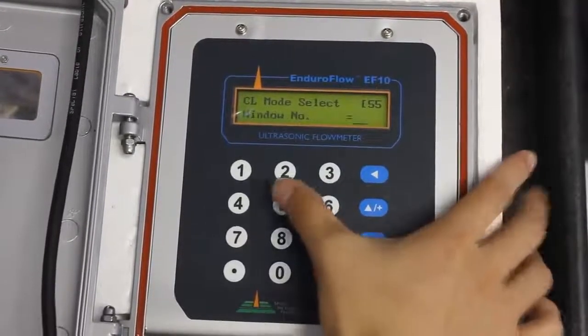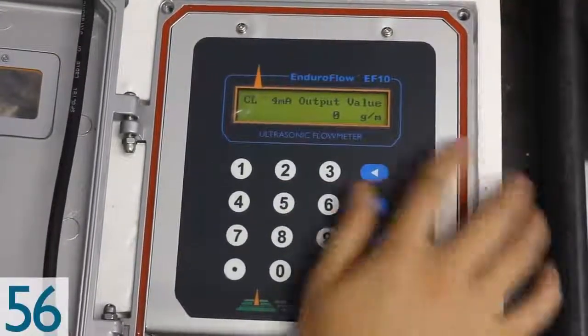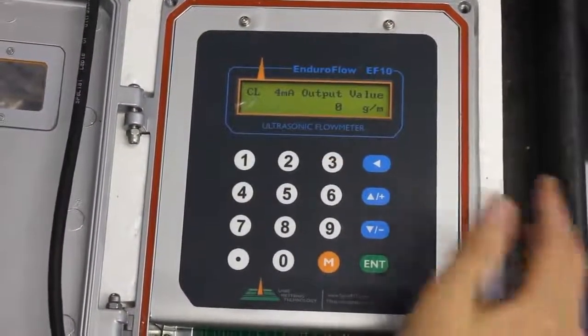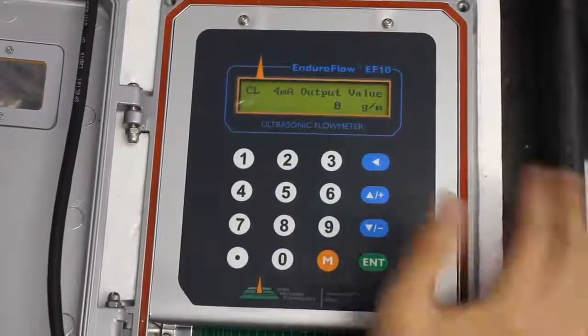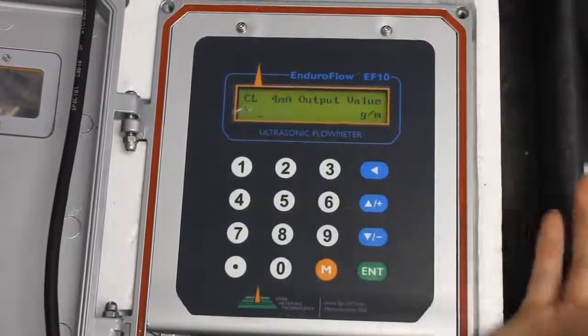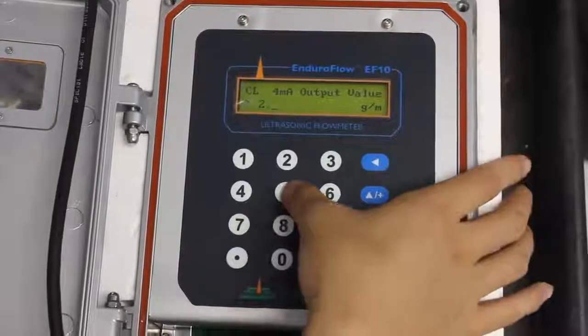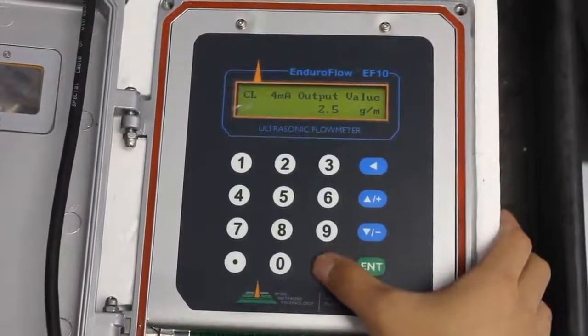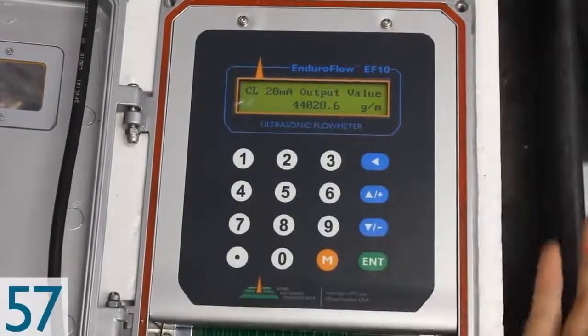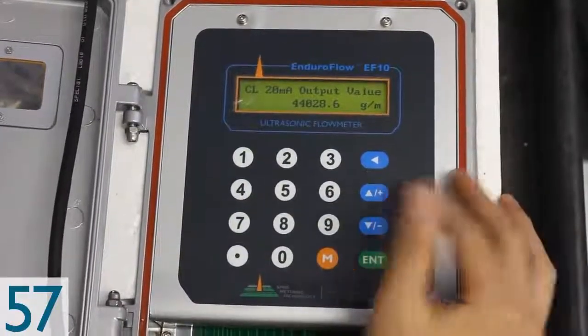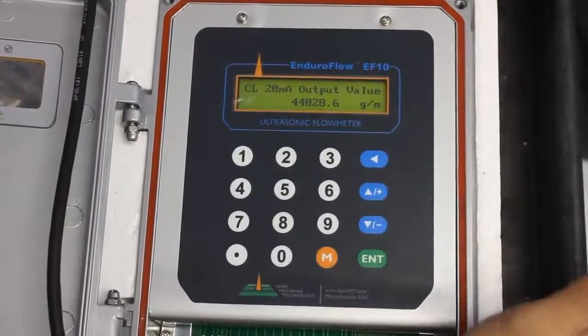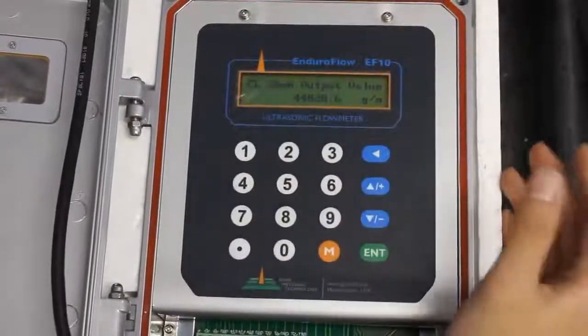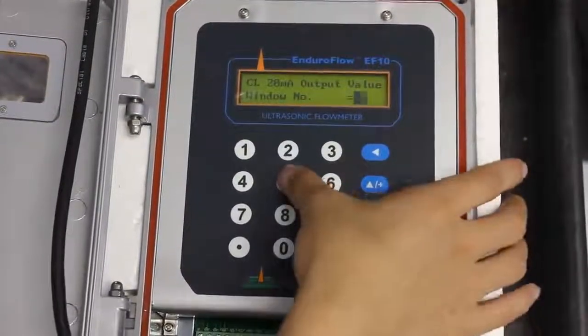Next you go to menu 56. And here you're going to select, set the flow rate slash energy value corresponding to the 4 milliamp current. Let's just say it was like 2.5. Okay. Next you go to menu 57. And here you set the flow rate or energy value corresponding to 20 milliamp current. Once you've selected the values that you need, you go to menu 59. And here it's going to show you the current output of the flow.